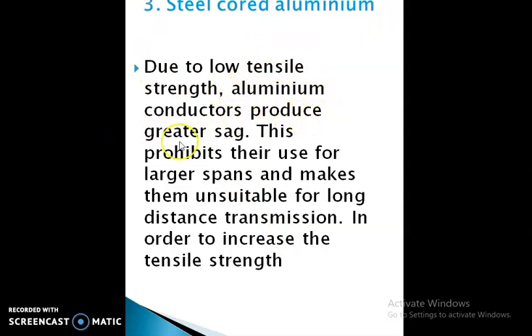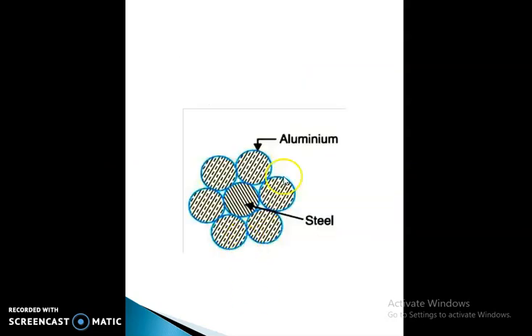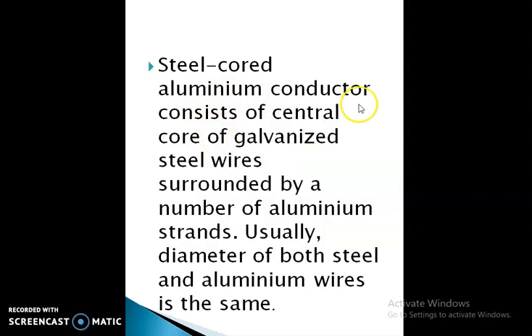The third type is steel-cored aluminum (ACSR - Aluminum Conductor Steel Reinforced). Due to low tensile strength, aluminum conductors produce greater sag, which prohibits their use for larger spans and makes them unsuitable for long-distance transmission. To increase tensile strength, the aluminum conductor is reinforced with a core of galvanized steel wire. The steel-cored aluminum conductor consists of a central core of galvanized steel wires surrounded by a number of aluminum strands. Usually the diameter of both steel and aluminum wires is the same.